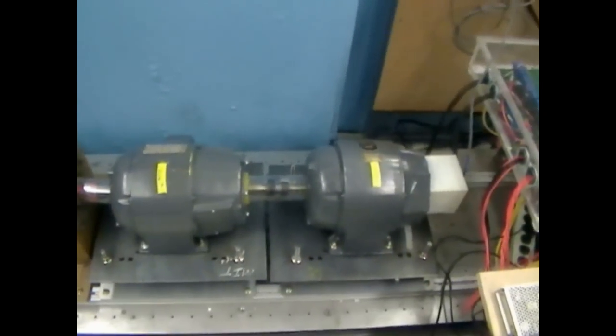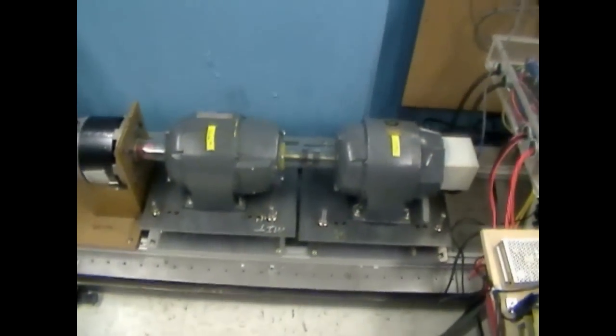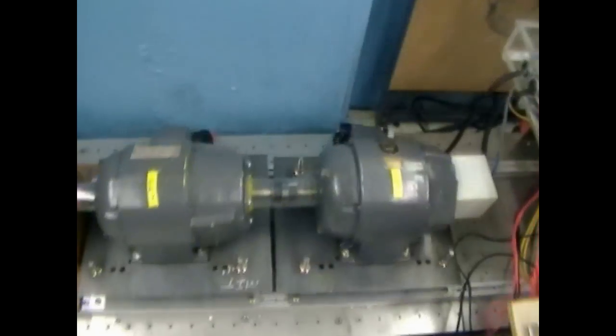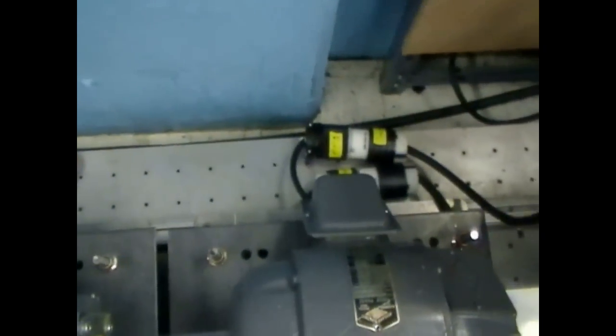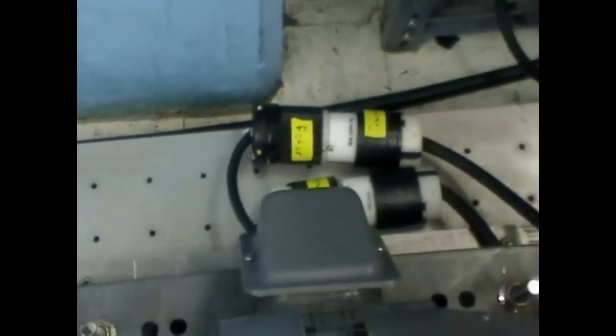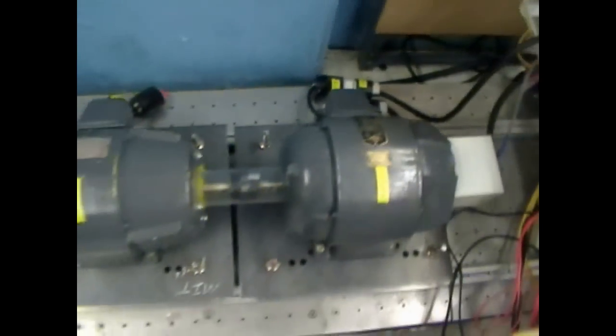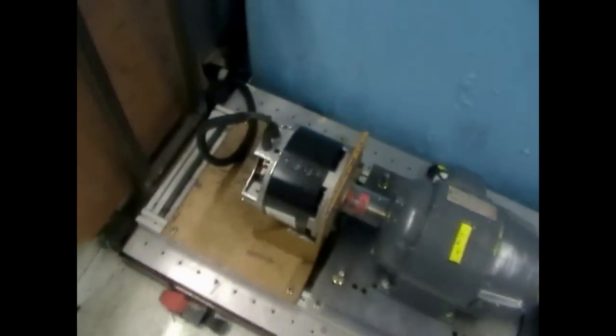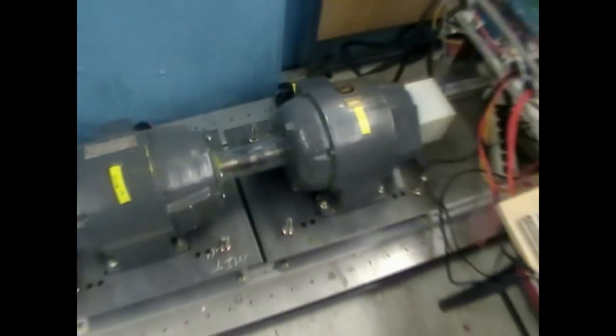So here is the doubly fed motor we'll be testing. As you can see, it is connected to two electrical ports through which the power enters, and we can access both the stator and the rotor windings. On the same shaft you can see this permanent magnet generator which is attached, and this acts as a load to this doubly fed motor.